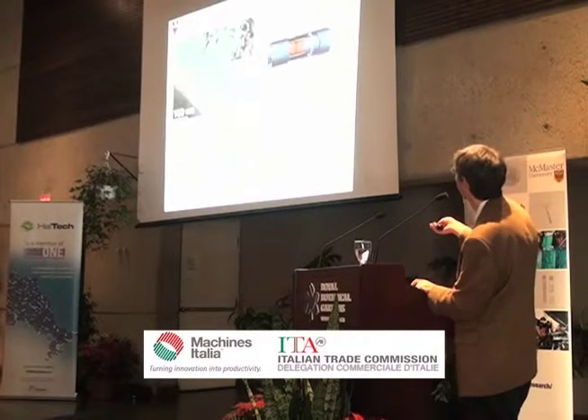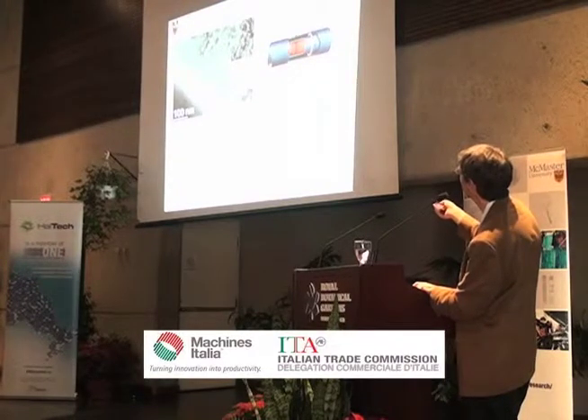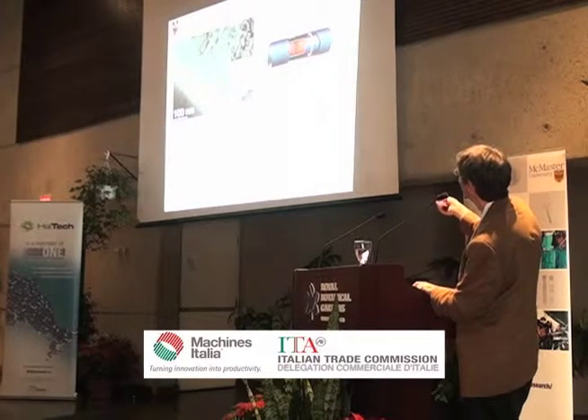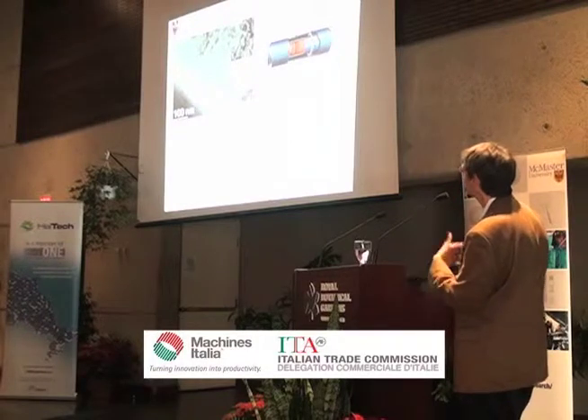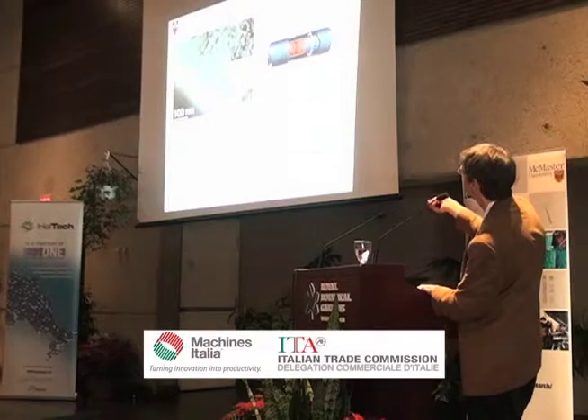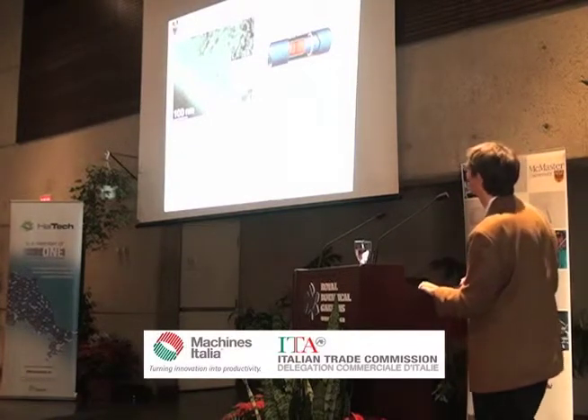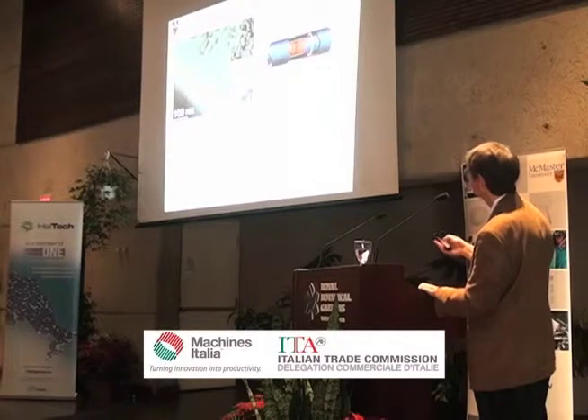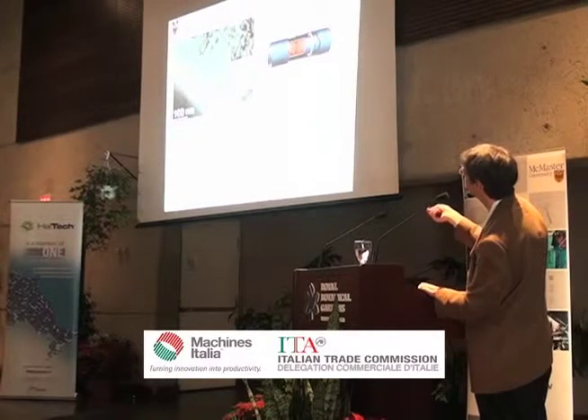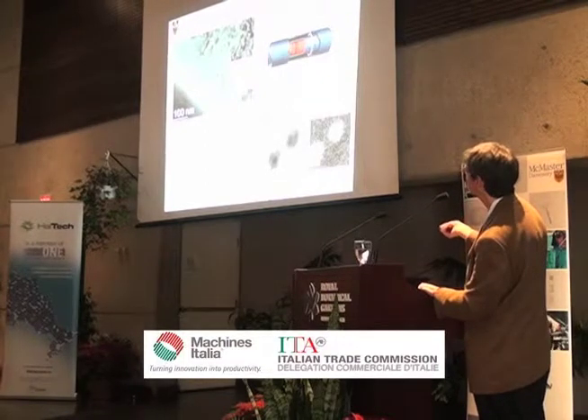One of the problems that has been observed is that following irradiation, some of these materials, these springs here, evolve with time. After decades of operation, they form small bubbles in these reactors. And we want to understand whether they're going to be an issue in terms of operation. So what we are able to see from these bubbles, which are a few nanometers in size, is that we can determine that they contain helium.